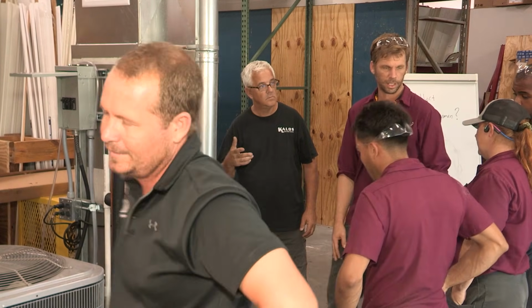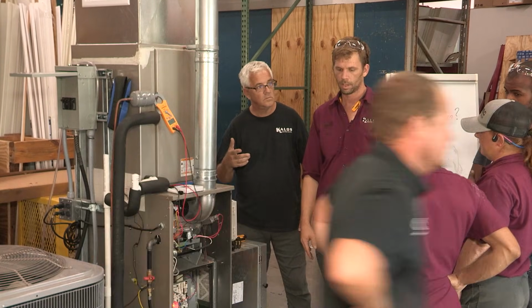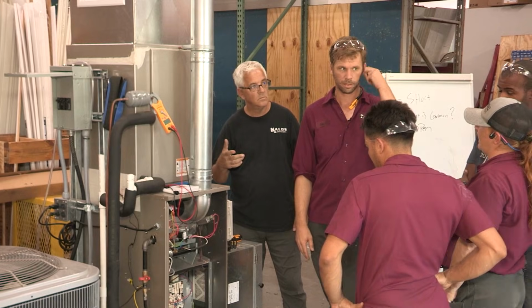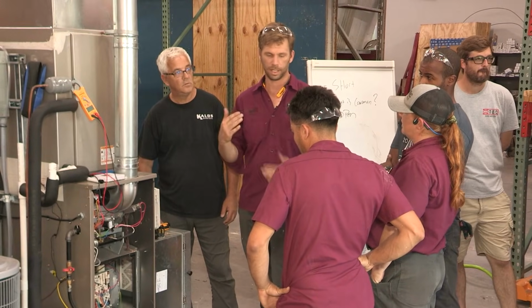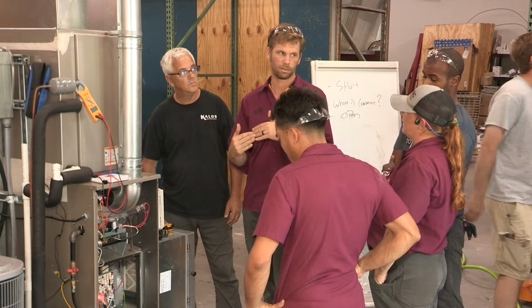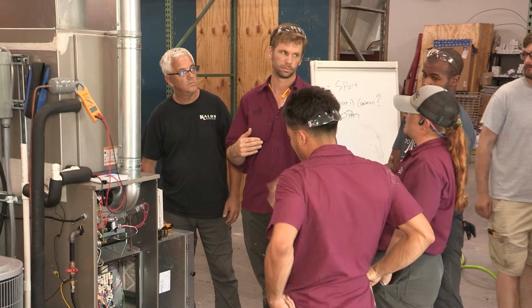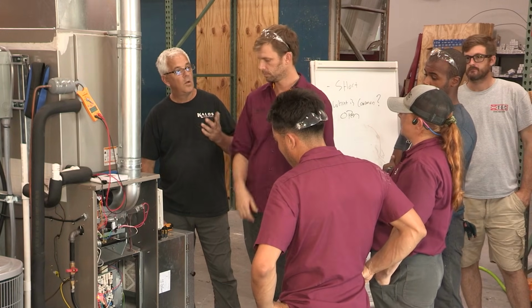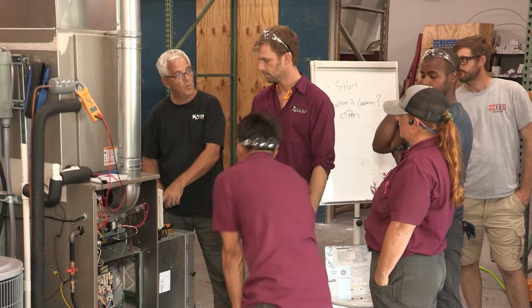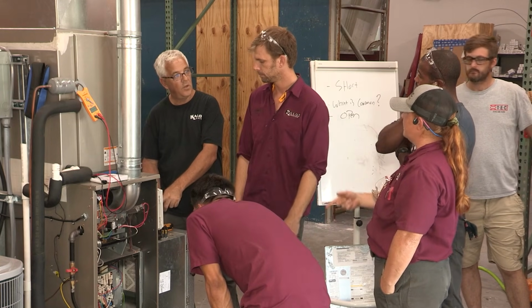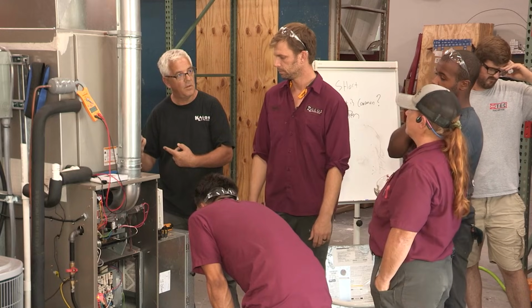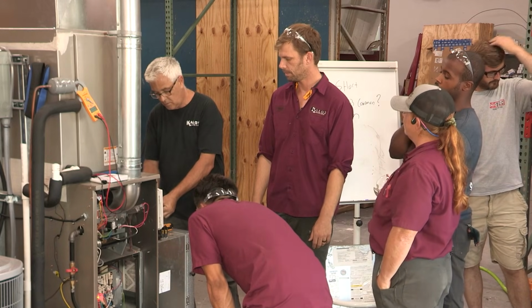So it's gotta be on Y, and our time delay is connected to our Y call. So it tried to run and it reset because it wasn't getting power. Now we could disconnect the Y, leave the other two connected, and see if the blower comes on with green and red.